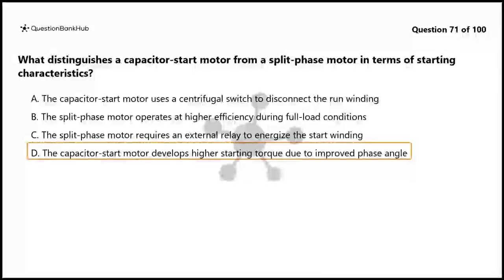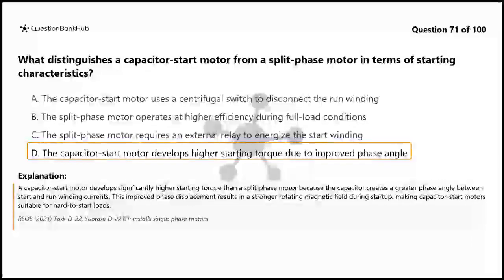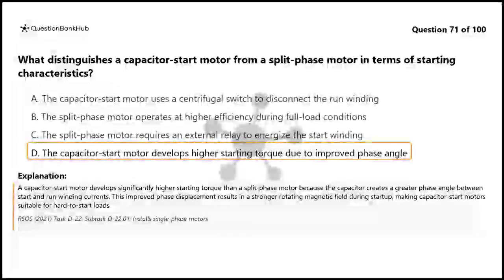The correct answer is D. The capacitor start motor develops higher starting torque due to improved phase angle. A capacitor start motor develops significantly higher starting torque than a split-phase motor because the capacitor creates a greater phase angle between start and run winding currents. This improved phase displacement results in a stronger rotating magnetic field during startup, making capacitor start motors suitable for hard-to-start loads.